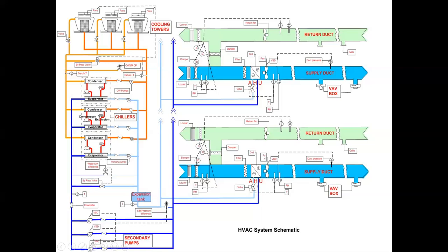So some of those, if it's a commercial space, might blow all the time, but they start and stop the compressor, which starts and stops the cooling or the heating. You blow cold air or warm air, and then when the thermostat says it needs cooling again, it kicks on the compressor and then it blows cold air. So you're cycling that. Well, with this VAV box, we keep about the same conditions in the duct, and the thermostat modulates this damper, which keeps the temperature in the space nice and happy. It's a more sophisticated, better arrangement.